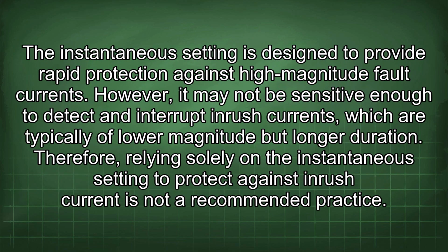The instantaneous setting is designed to provide rapid protection against high-magnitude fault currents. However, it may not be sensitive enough to detect and interrupt inrush currents, which are typically of low magnitude but longer duration. Therefore, relying solely on the instantaneous setting to protect against inrush current is not a recommended practice.